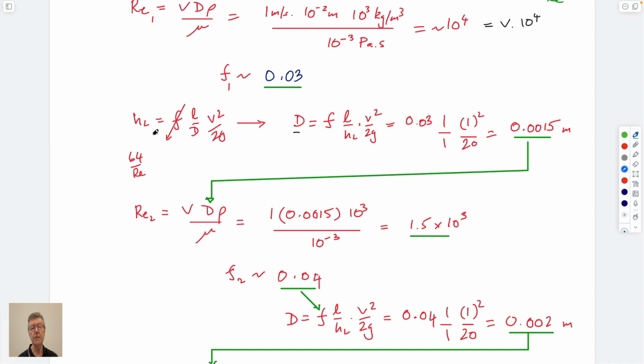Now with our head loss equation, we have a value for friction factor. We substitute that in by rearranging for the diameter, which we want to solve for. We take the head loss equation from before, but instead of rearranging for velocity, we rearrange for diameter. With friction factor, 1 meter long, head loss of 1 meter, velocity of 1 meter squared, and 2g (9.81 times 2 is 20), it comes out to 0.0015 meters for diameter—so this is 0.15 centimeters.